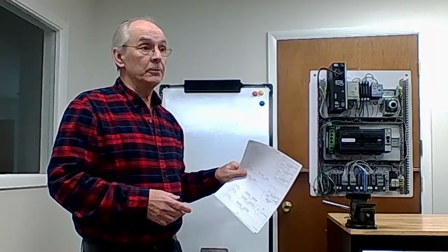Relay ladder logic. So one of the reasons that PLCs are popular in controls is because once the controls are in a plant, it's the maintenance guys that have to take care of it. And the maintenance guys have to be able to troubleshoot it and figure out if there's a problem and so forth. So by making the programming of the PLC look exactly like the wiring diagram that the old timers were familiar with, and still have in the plant to troubleshoot, it made things a lot simpler because then they didn't have to learn another language.